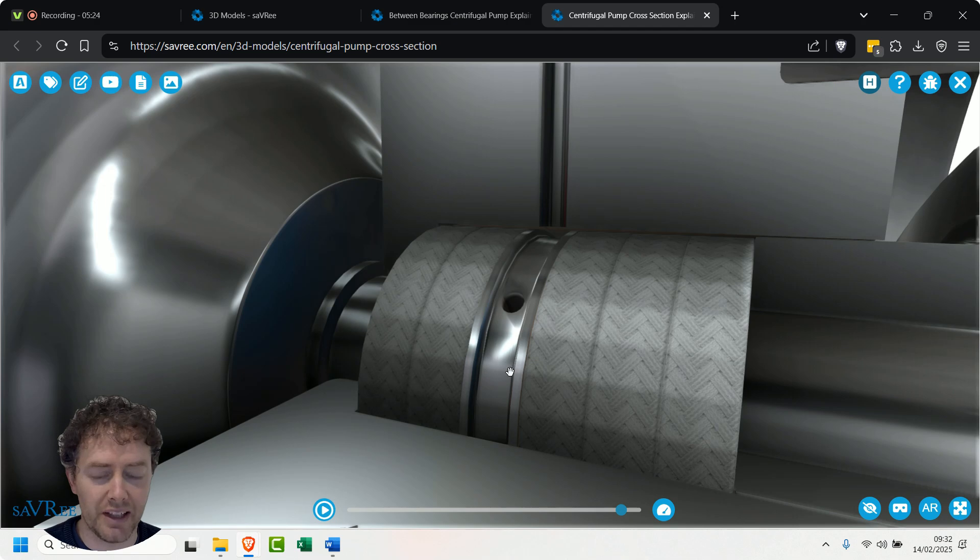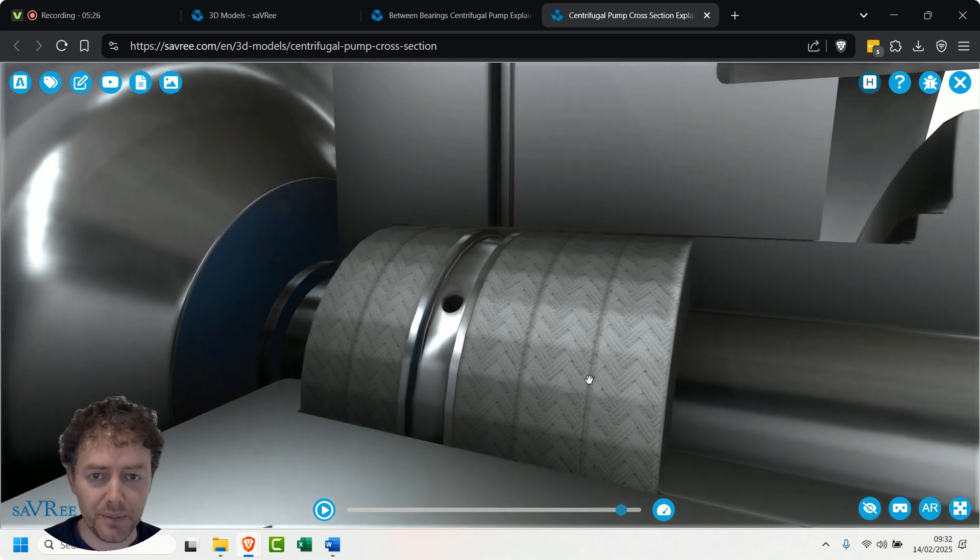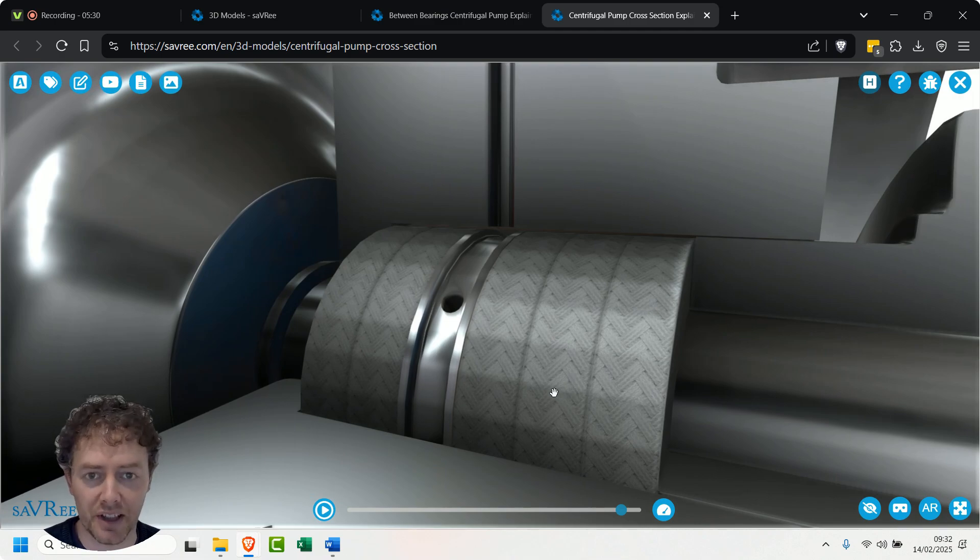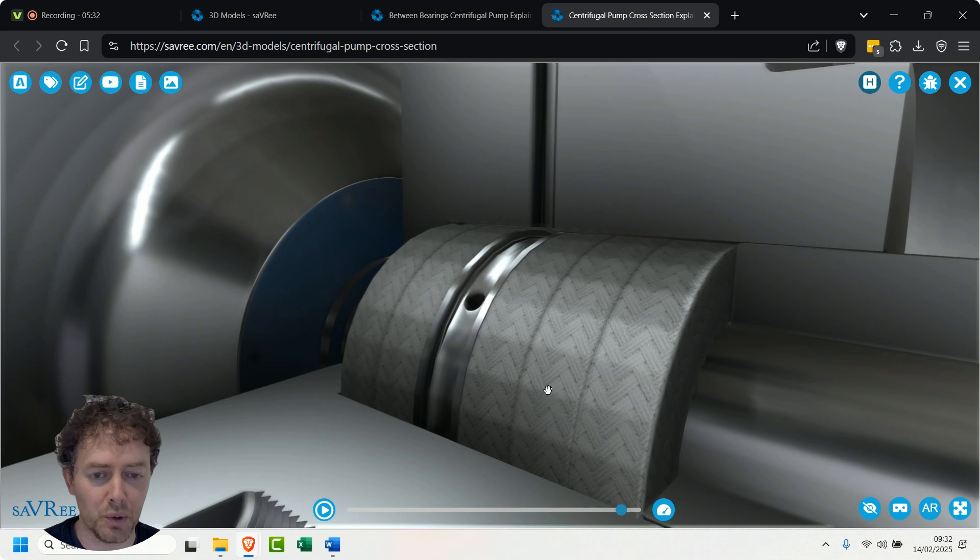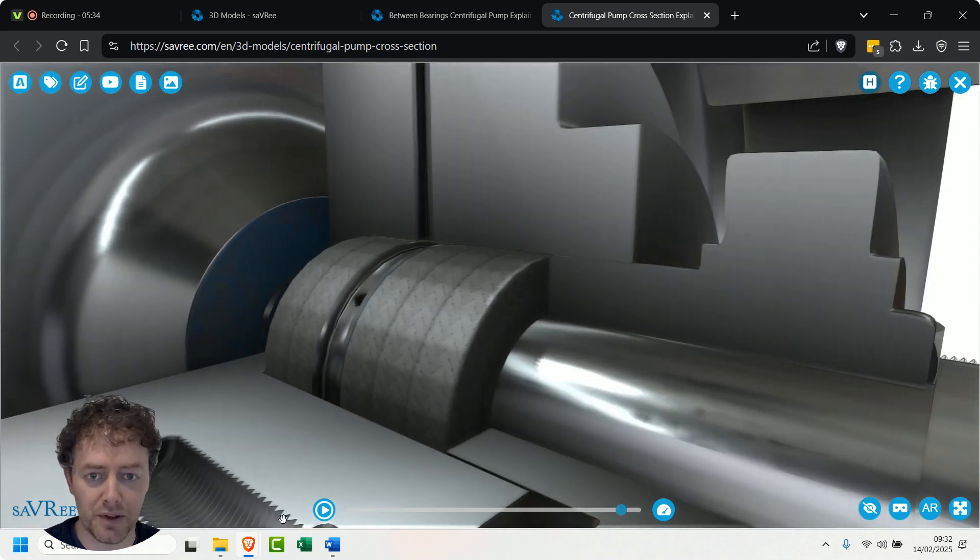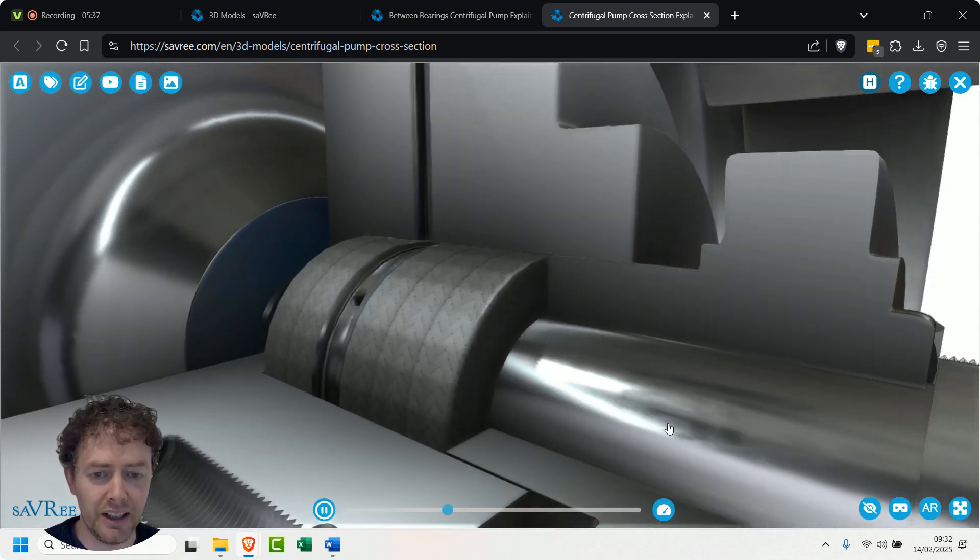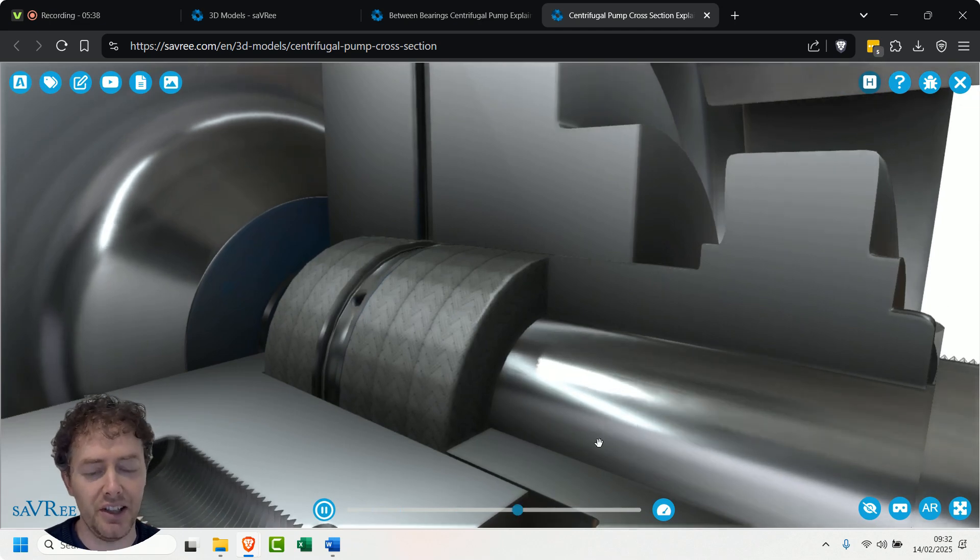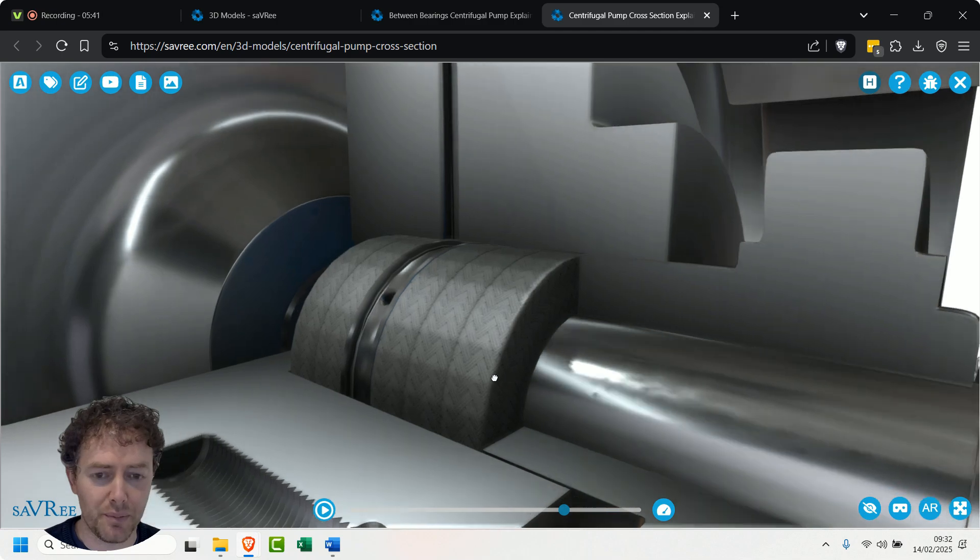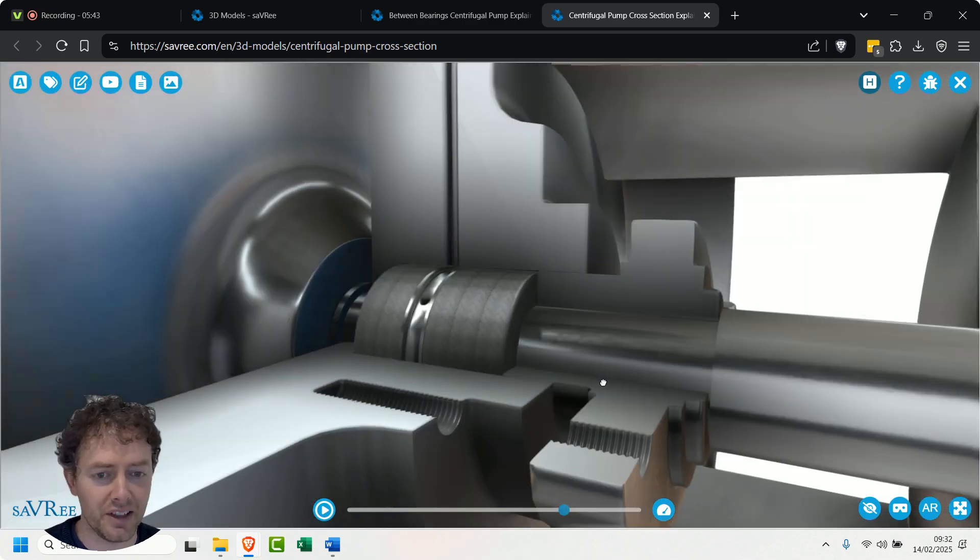And the idea is that you're lubricating the rope material - and the reason you do this, or lubricating the packing I should say - the reason you do this is to keep it cool. So when the pump is rotating, you've got the shaft rotating quite quickly, it generates heat due to friction. And what you've done with this packing material is you've compressed it using a follower.